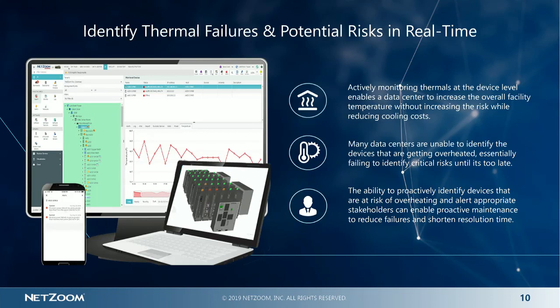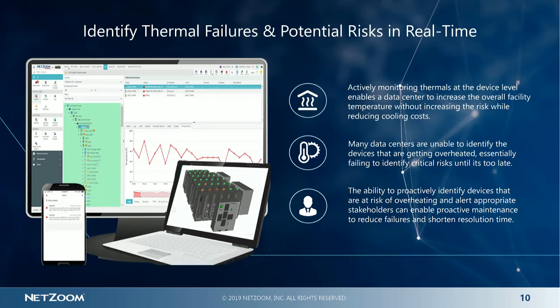If that sounds too cozy to be an incentive, remember we're looking at savings of about $200,000 or more annually on reduced cooling capacity alone for a 300 rack data center, not counting the savings from decommissioning the thermal sensors themselves. If your data center is bigger, these savings shoot up.